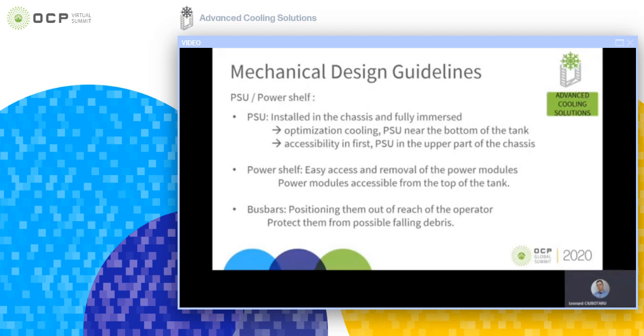From the accessibility point of view, the power shelf presents obvious advantages. The power modules are accessible from the top of the tank, which facilitates servicing or replacement. If a power shelf is used, most probably the tank will have a busbar installed. We recommend that this busbar be positioned out of reach of the operator and protected from possible falling debris. Also, the servers should be designed in such a way that some sort of hard stop can provide security from damaging the power connector if the server is dropped or badly placed.